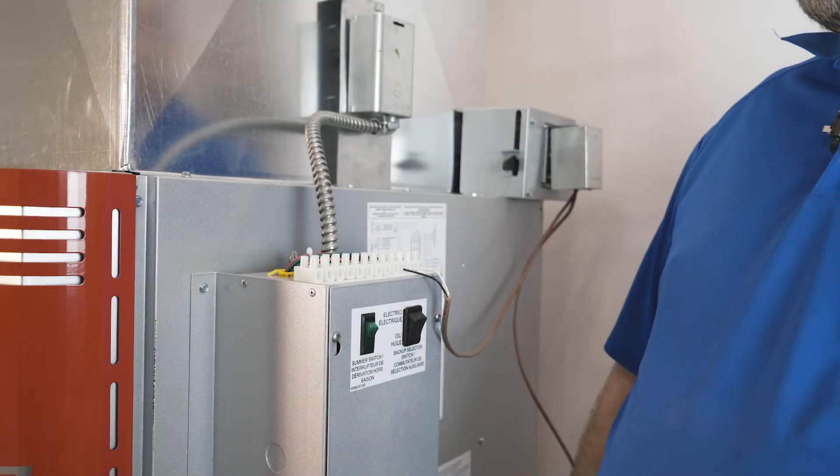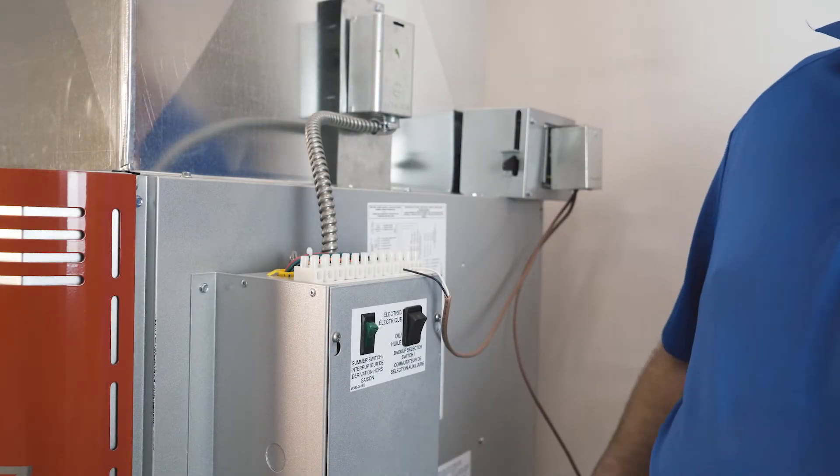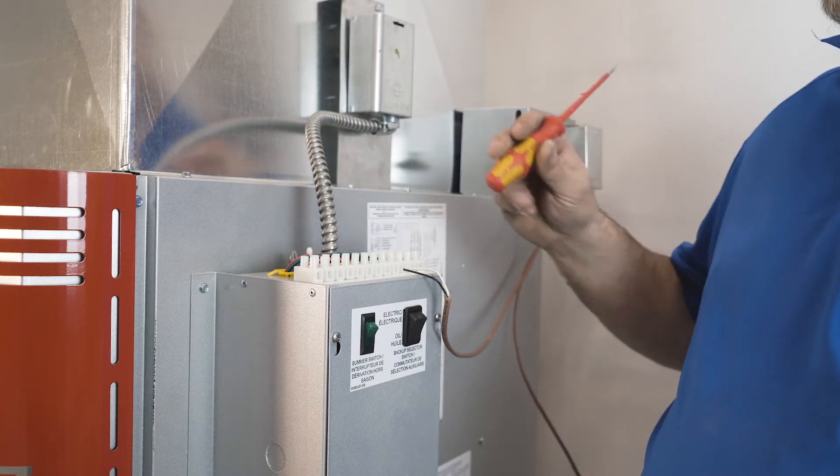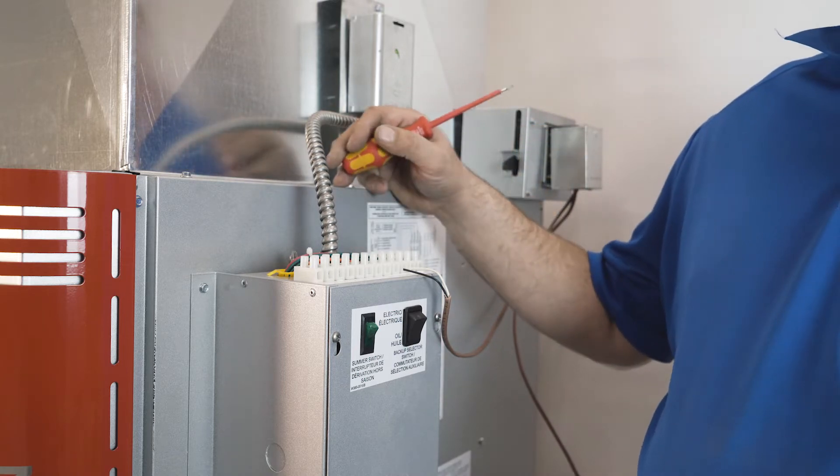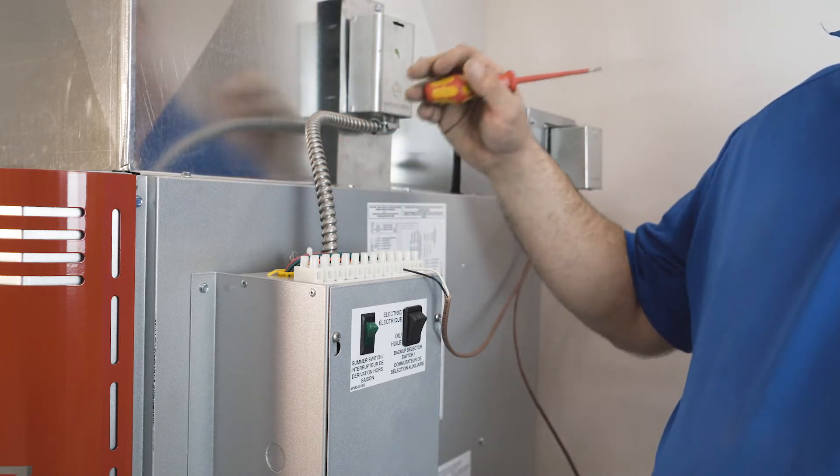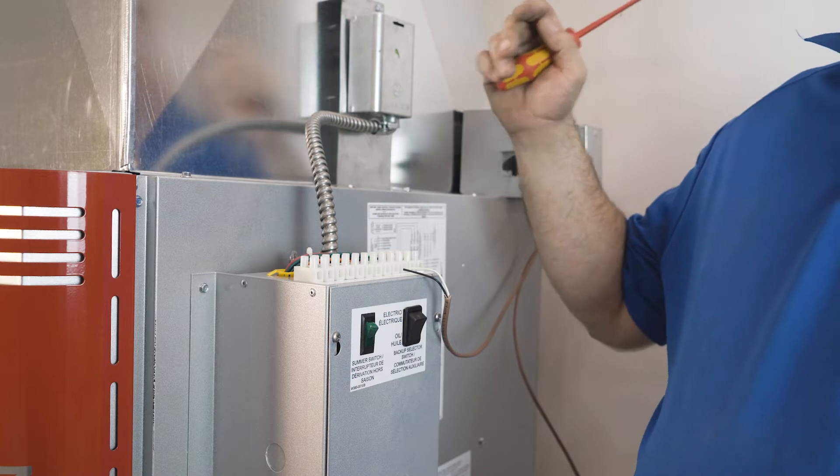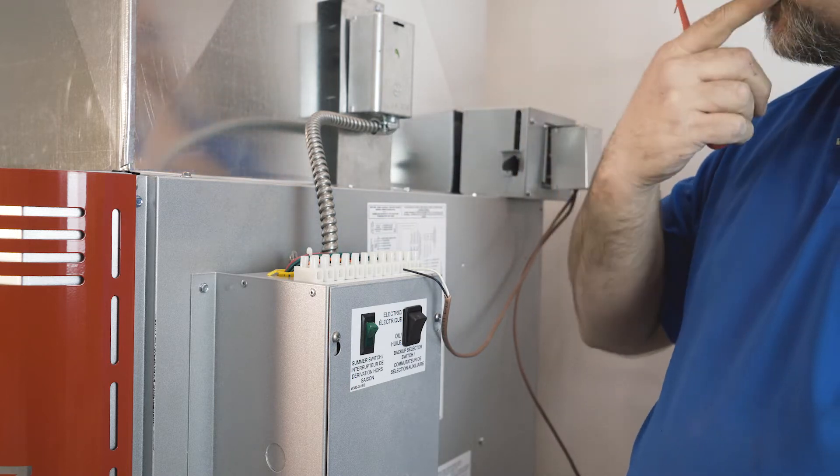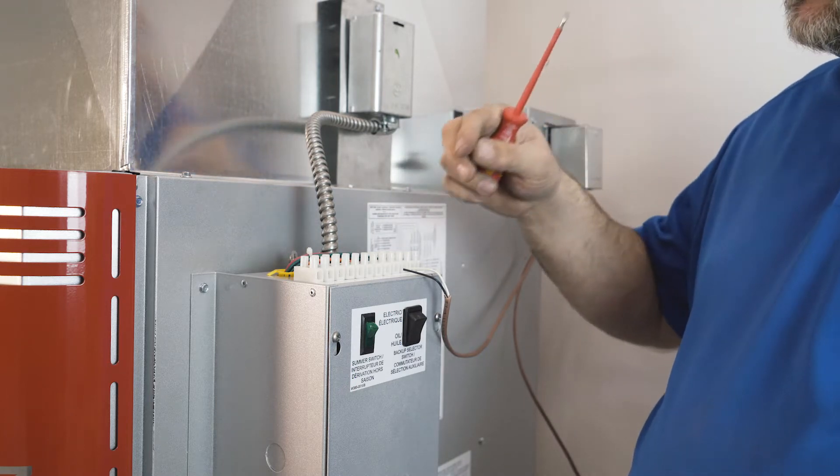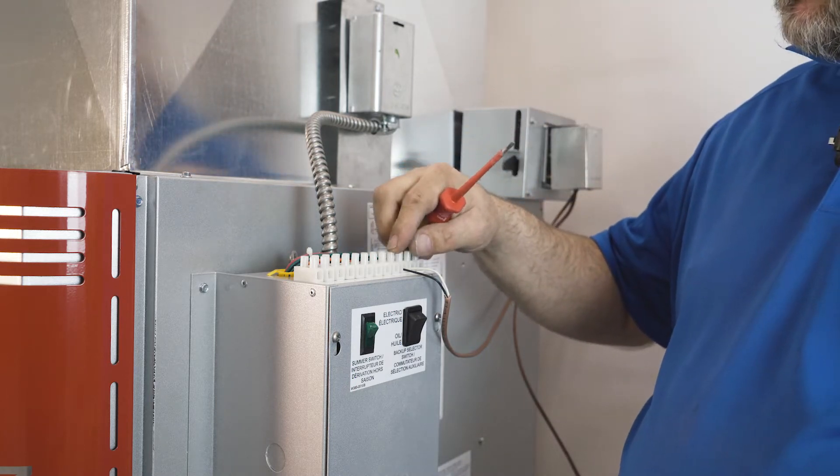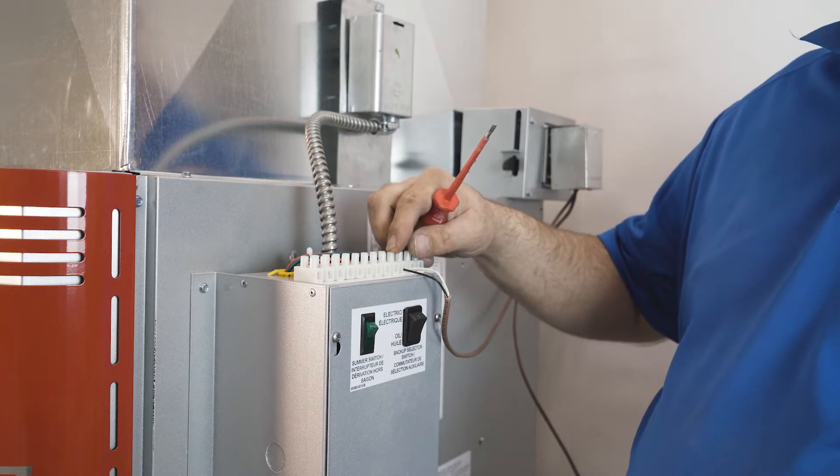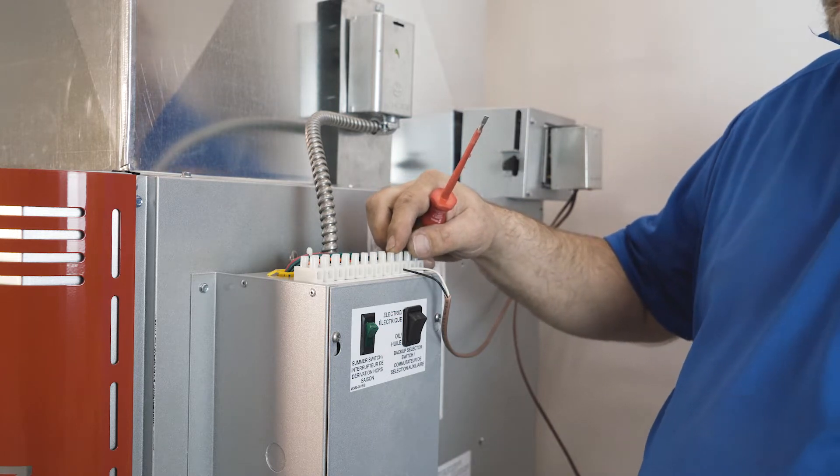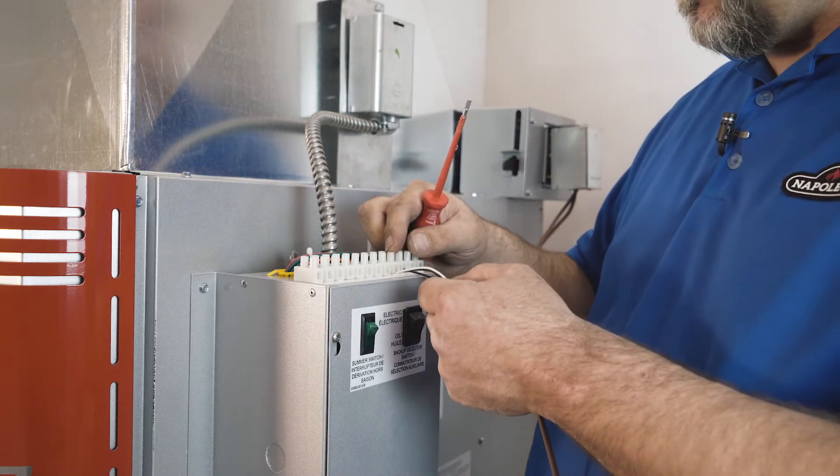We're going to install electric backup heat with our HMF 150 wood-burning furnace. We've already run some wires down from the thermostat upstairs. Thermostat connections for electric heat go on the 8 and 9 section here at the top of the controller.